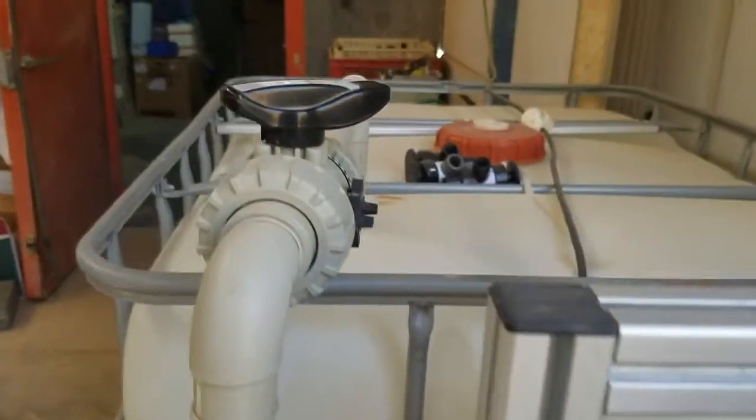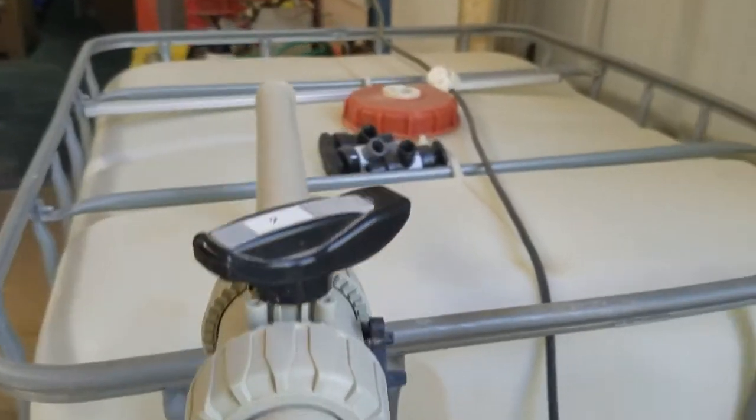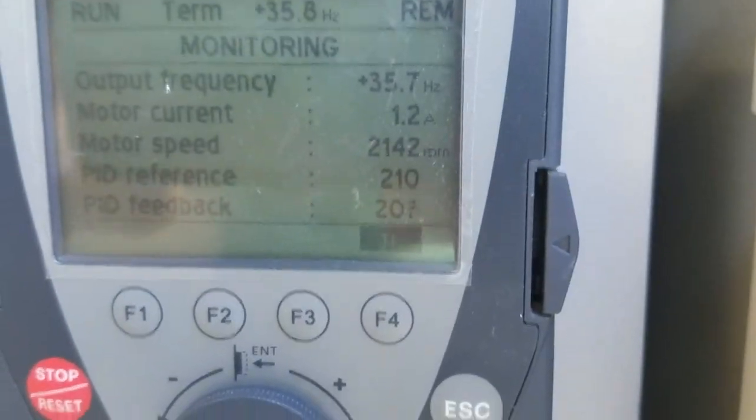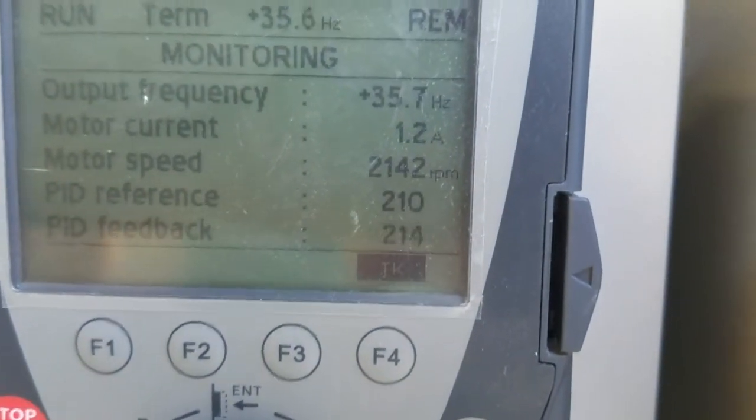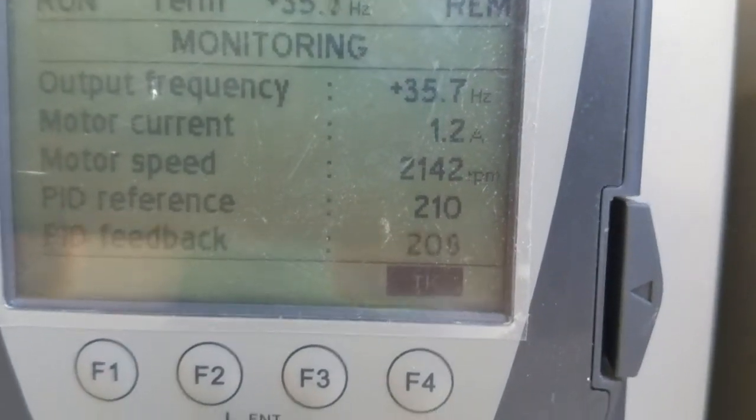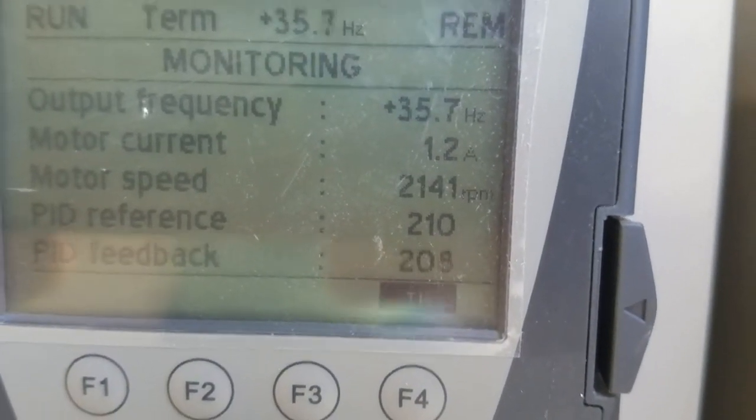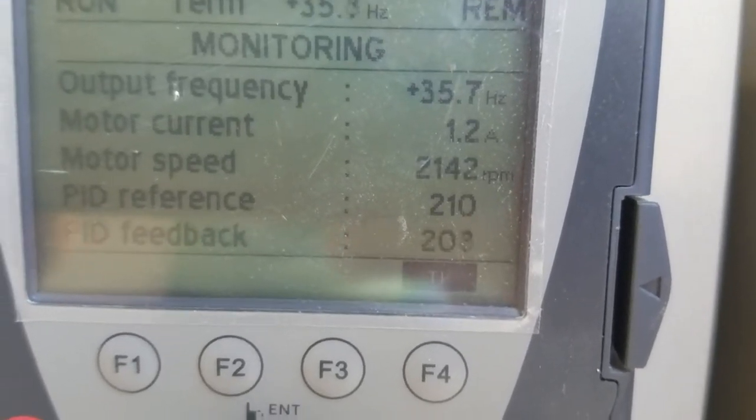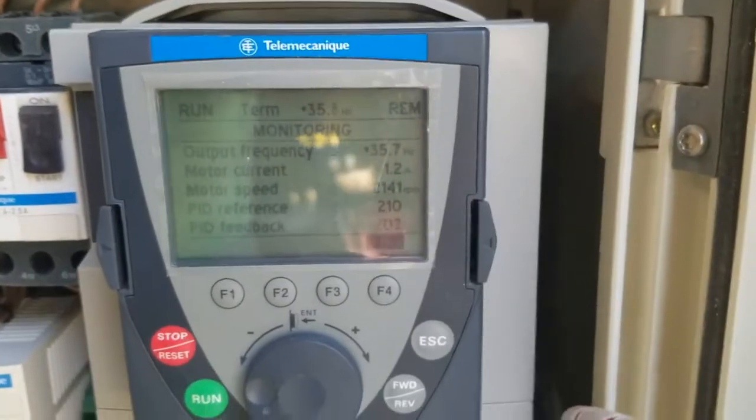Because the valve is partly obstructed, as you can see, the VSD is only turning at 35 hertz, which is only about half of the speed—a little bit more than half. Now I will open the valve a little bit.